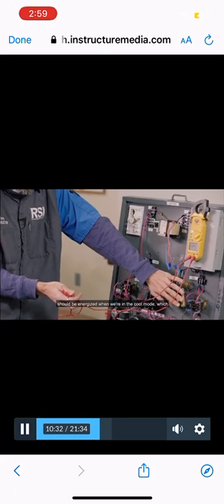Okay, now on this particular unit, it's using the O terminal, which means this reversing valve here should be energized when we're in the cool mode, which we are. Okay, so I went to this relay over here on the coil, just like we did with the blower, and I'm looking for voltage.